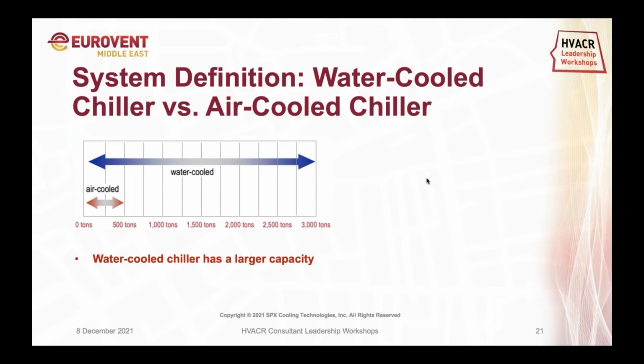Now, a small comparison between the air-cooled capacity and the water-cooled capacity. The air-cooled is limited almost to 450 to 500 ton maximum, and it cannot go beyond that, while the water-cooled chiller can even go to 3,000, and in the recent couple of years I have seen chillers go to 3,500 ton and even more with the double compressor type of chillers.